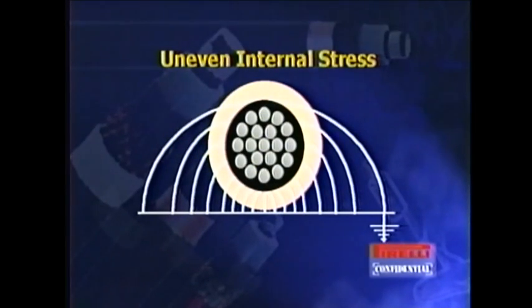As we implied before, there's a direct relationship between the magnitude of the voltage and the amount of insulation that you extrude onto the conductor. The larger the voltage or the higher the voltage, the more insulating material that you have to put on. And this assumes that you're going to have an even voltage stress around the entire circumference of the cable. Therefore, in order to obtain this, we have to have a constant potential around the outside of the circumference. Assuming that you don't have any conductive material around the circumference of the dielectric, and you lay this cable onto a ground plane, the electric field will be distorted in the direction of the ground plane.